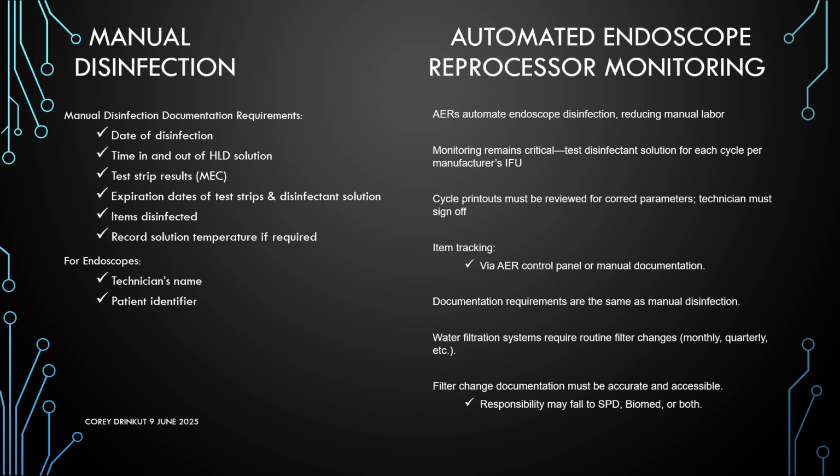So the AERs usually use micron water filters that require scheduled replacements. We do not replace those ourselves. We call maintenance. They replace it. It's on a set schedule, so we don't have to worry about it. It is replaced, it is tagged, it is documented by maintenance or the facility. We do not touch it. Whether it's through biomed, it must be documented. And usually, whoever replaces it does the documentation.